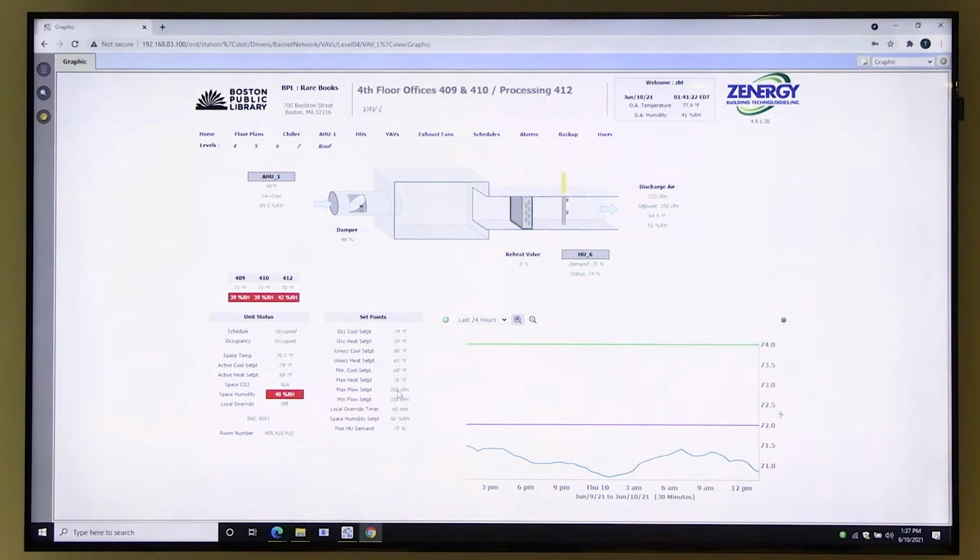This is a constant volume box. I think for the most part they all are. I can click through some of them and see if any of them aren't constant volume. But because this one has the same minimum and maximum flow, basically there's no way it's not going to do anything to cool the space. Typically on a VAV box, you would allow more air in to cool the space. Because your maximum is the same as your minimum, you're just always going to be looking for this 350 CFM here. So you're always trying to bring in 350 CFM.